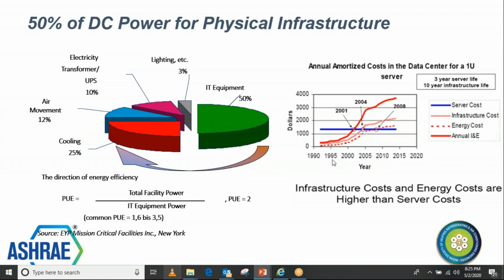So on the right side you can see why this is important. Your cost of electricity and cost of real estate are both going up. They are not coming down at all, and the server cost is not changing much. So this change in real estate and electricity cost is driving the efficiency factors in precision AC. Precision AC must consume much, much lower power, and our focus should be on achieving good PUE levels. Just to give you an idea, traditional data centers are typically around 1.7 to 2 PUE levels.